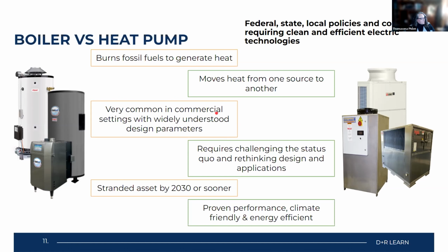However, with the heat pump water heating system, design has been an issue coming up through the last 10 years, and figuring out the best size, the best capacity based on load, usage, climate, entering water temperature, the whole bit. This has been a big learning curve, but it does require challenging the status quo and rethinking the design in applications. Because the heat pump itself doesn't really have that large a footprint. It's about the size of a refrigerator, most of them, but the water storage is significant.